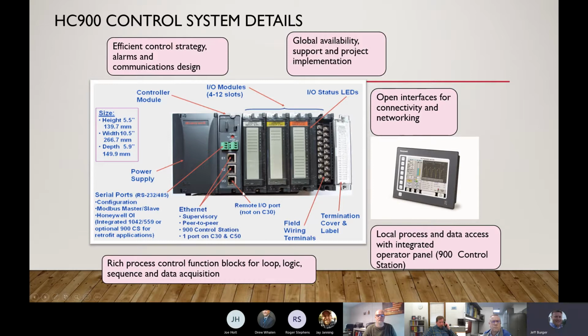If you want to use an Ethernet port, you can have a couple different options here for Ethernet. You have the very top one, which is your Ethernet E1 port, and this is used for communicating up to, like, an Experion HS or LX SCADA software. It could also be used to communicate up to, like, a SpecView software, or maybe a third-party software like Wonderware, something like that. But you can use that to communicate up to your supervisory level software.